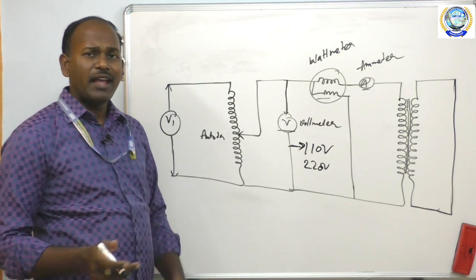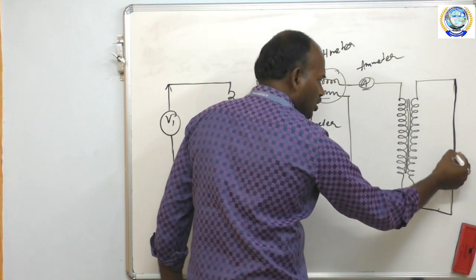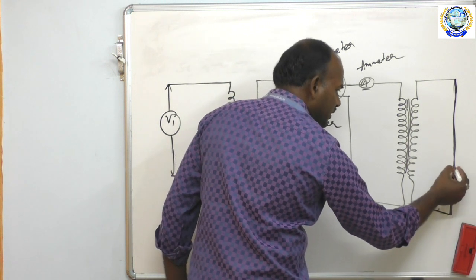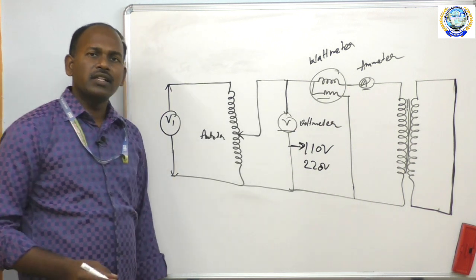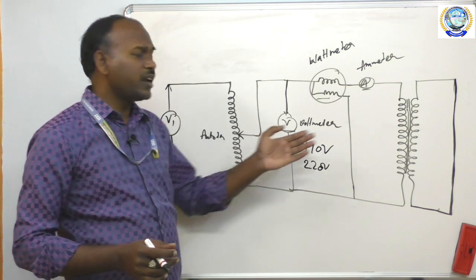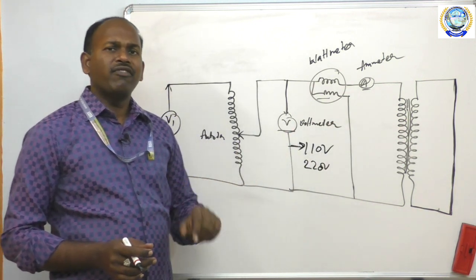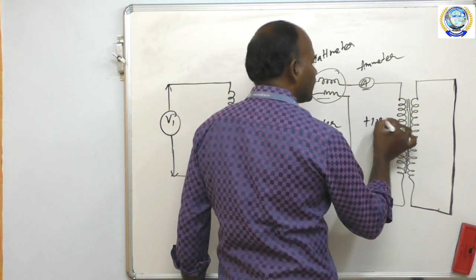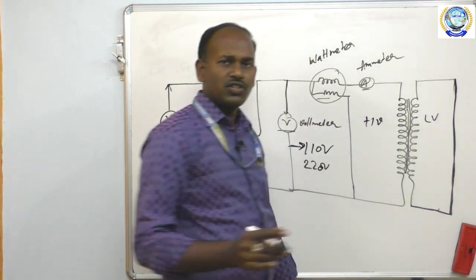Now let us consider the short circuit test. The circuit diagram for the open circuit test and short circuit test are the same with a simple difference: previously the secondary was open-circuited, and now it is short-circuited. In the same manner, either side of the transformer you connect the meters and short circuit, but preferably on the high voltage side you connect meters and the low voltage side is short-circuited.